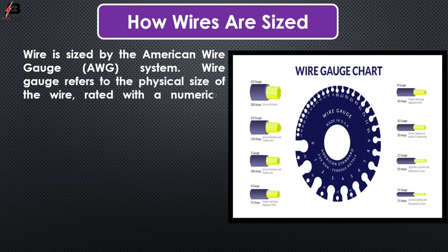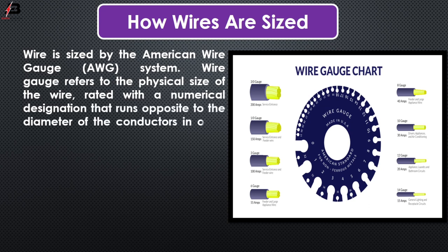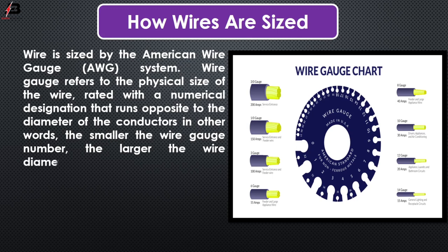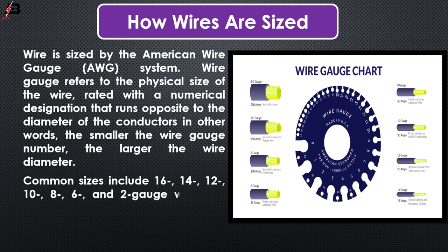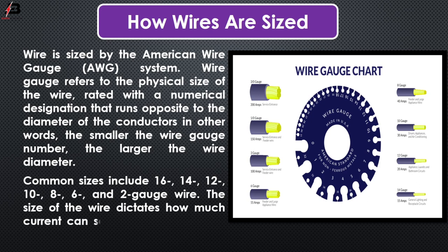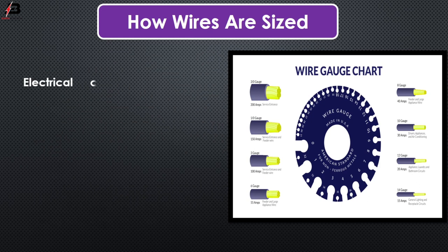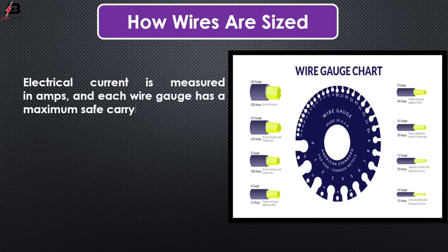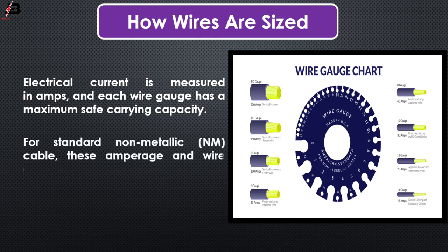Wire gauge refers to the physical size of the wire, rated with a numerical designation that runs opposite to the diameter of the conductors. In other words, the smaller the wire gauge number, the larger the wire diameter. Common sizes include 16, 14, 12, 10, 8, 6, and 2 gauge wire. The size of the wire determines how much current can safely pass through it. Electrical current is measured in amperes, and each wire gauge has a maximum current-carrying capacity.